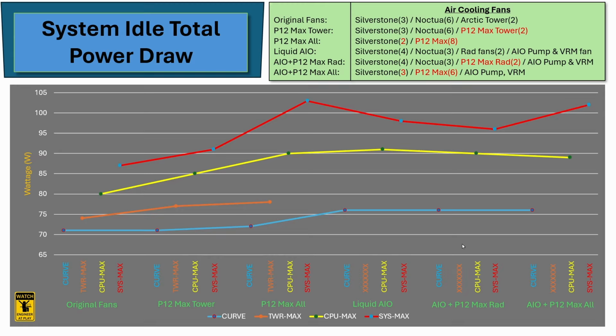One more thing I wanted to show was the power draw from changing out this hardware. I changed the chart a bit - instead of one line bouncing up and down across different fan control configurations, I drew separate lines. The blue lines are all the curves across the different hardware for air cooling versus liquid cooling. This is with the tower fans set to maximum speed on the air cooler tower - we don't have that option with liquid cooling since there's no tower with fans.